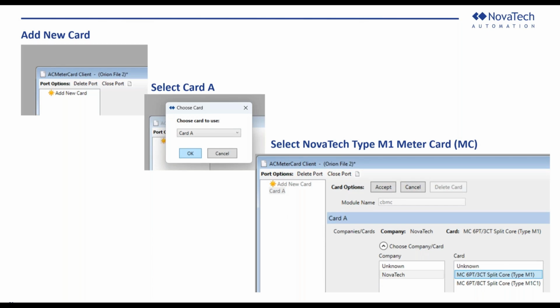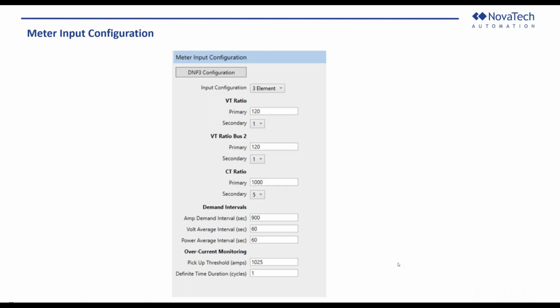From there, you would add a new card. It'll give you an option to select card A or B. So I'm choosing card A, and at the bottom of it, I'll choose NovaTech, and then I'm choosing the M1 meter card, which gives us the 6 PT and 3 CT with split core. Similarly, the same process can be repeated for card B, either if it's the same or you want to use the M1C1 card. After that's done, we would go into the meter input configuration.